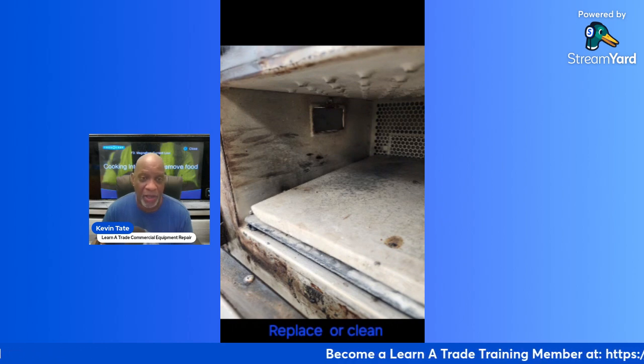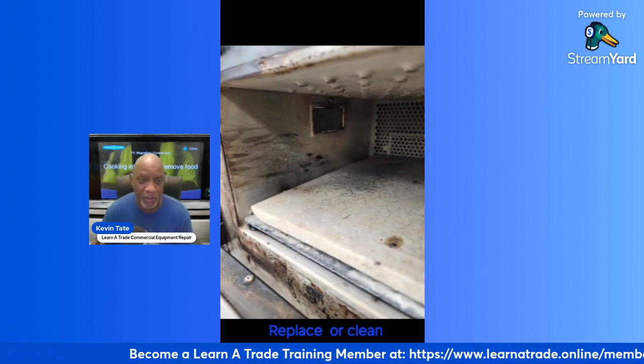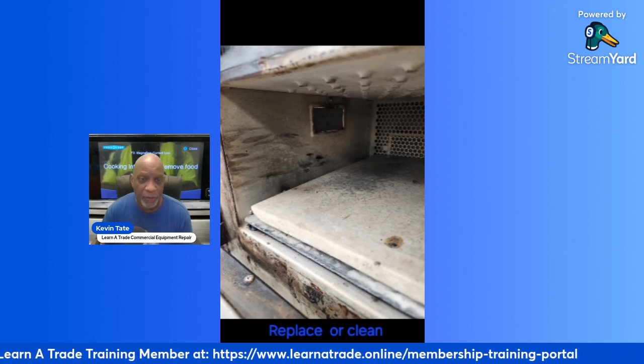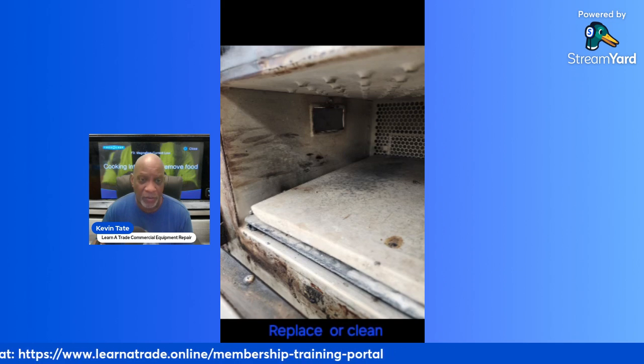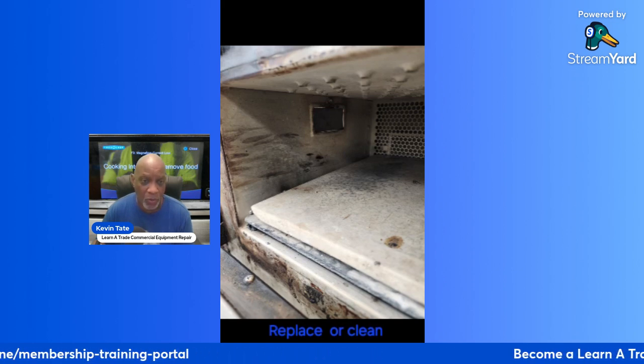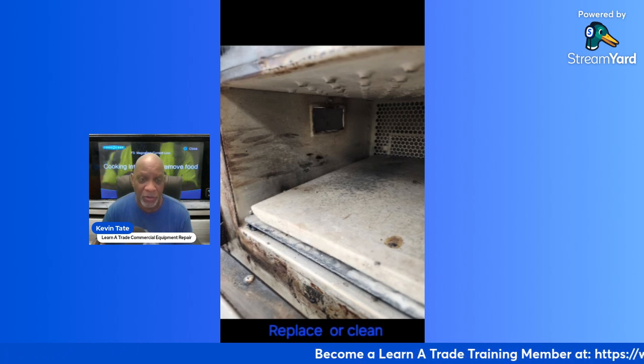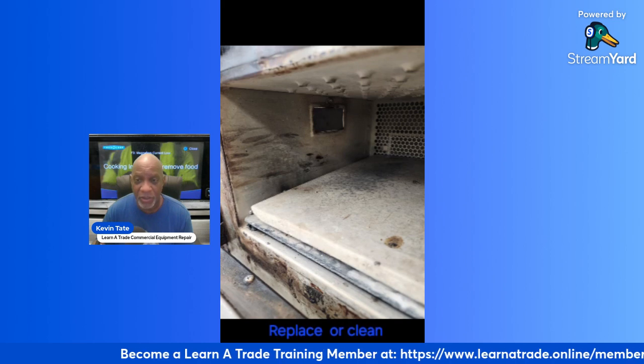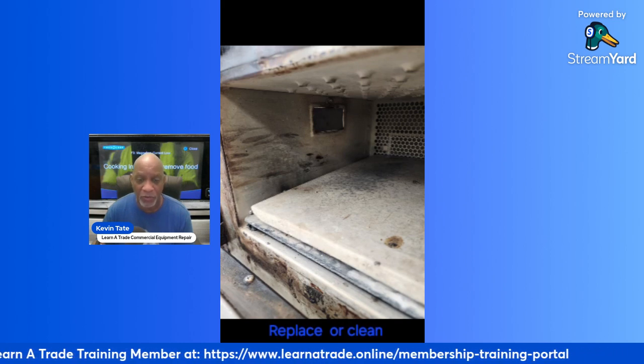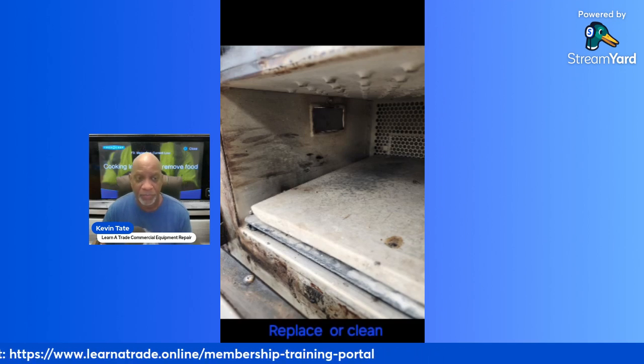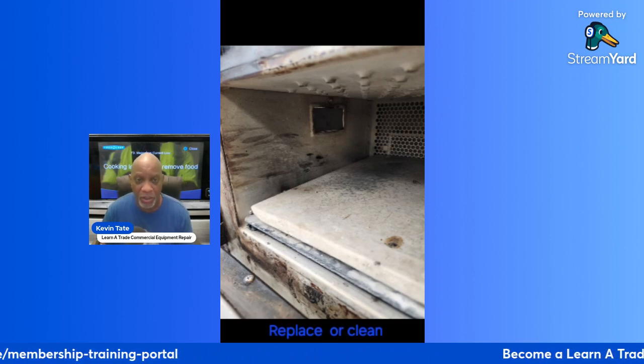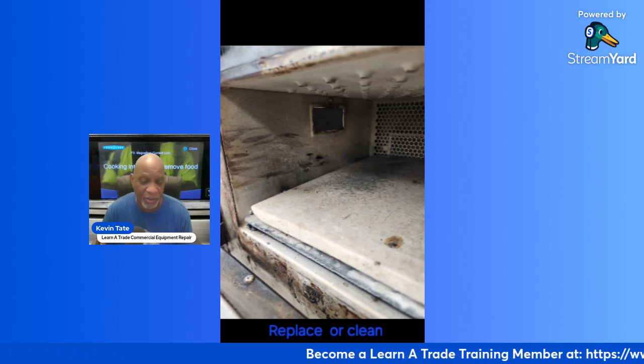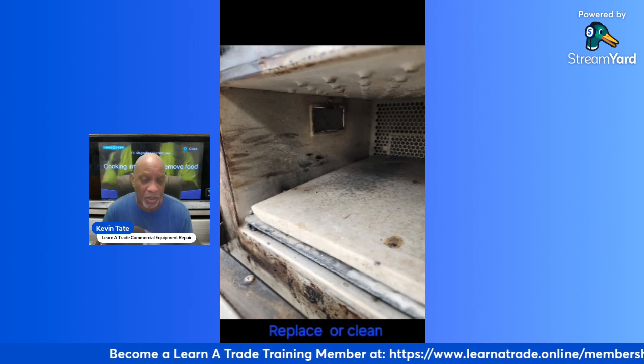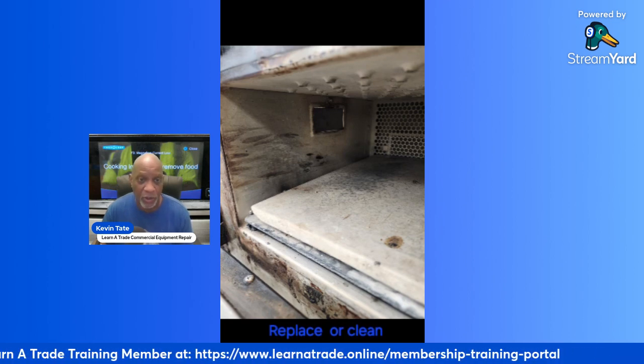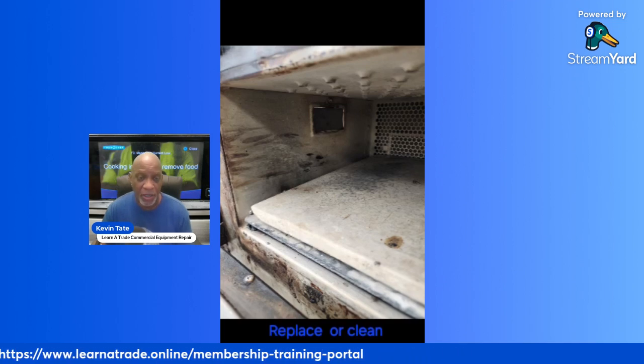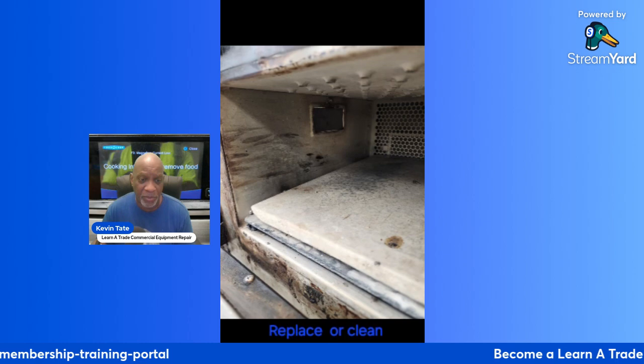These are the waveguide windows, right on the side wall there. That's the waveguide windows with the seal, and that's what I was talking about when you put in a quote. If you needed to replace the waveguide, you want to replace the window. You don't always have to replace the window, but a lot of times these windows are very difficult to get cleaned up, so it's usually better to just put in a new glass. But if you're able to clean the glass and get it clean, then that's fine too. You can just clean it, dry it off, and then put a new seal on there. I do recommend that you put a new seal on it, and then they can be back in business.